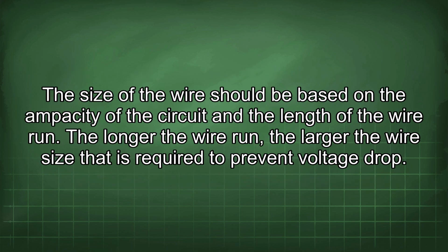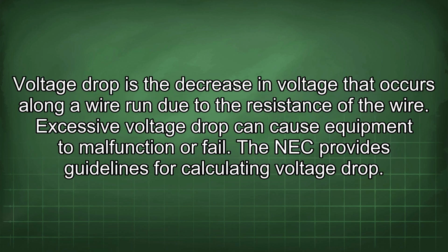The size of the wire should be based on the ampacity of the circuit and the length of the wire run. The longer the wire run, the larger the wire size that is required to prevent voltage drop. Voltage drop is the decrease in voltage that occurs along a wire run due to the resistance of the wire. Excessive voltage drop can cause equipment to malfunction or fail. The NEC provides guidelines for calculating voltage drop.